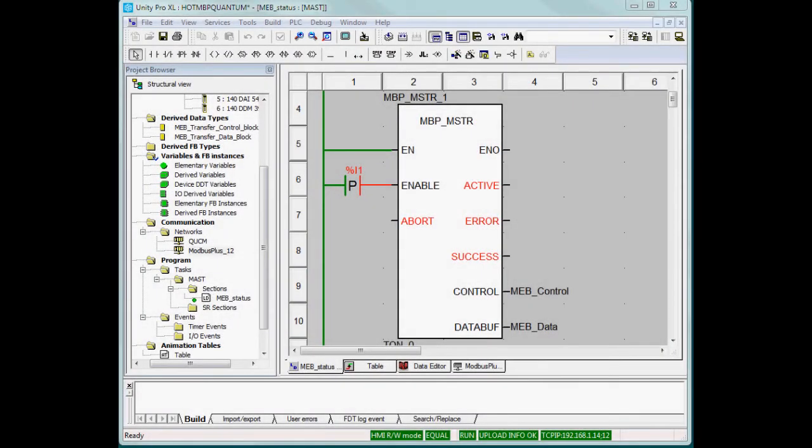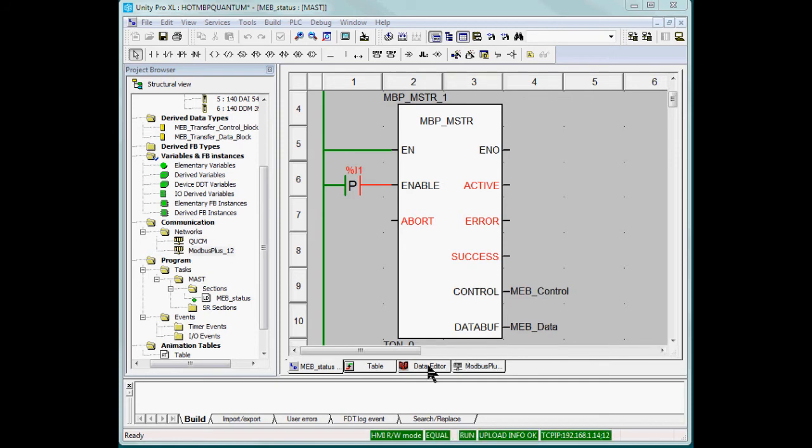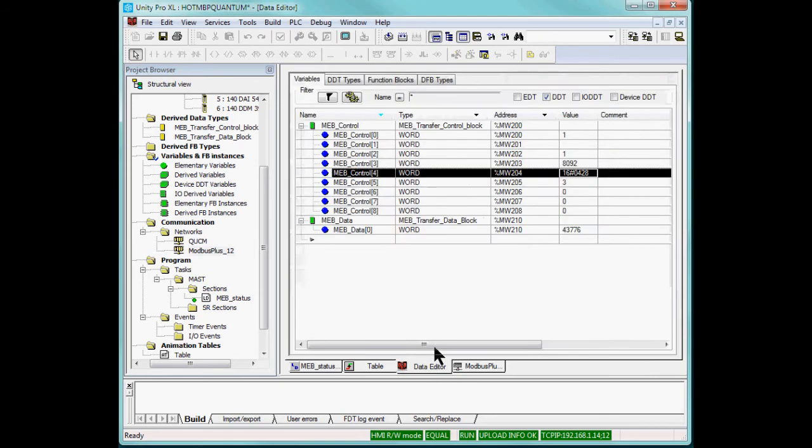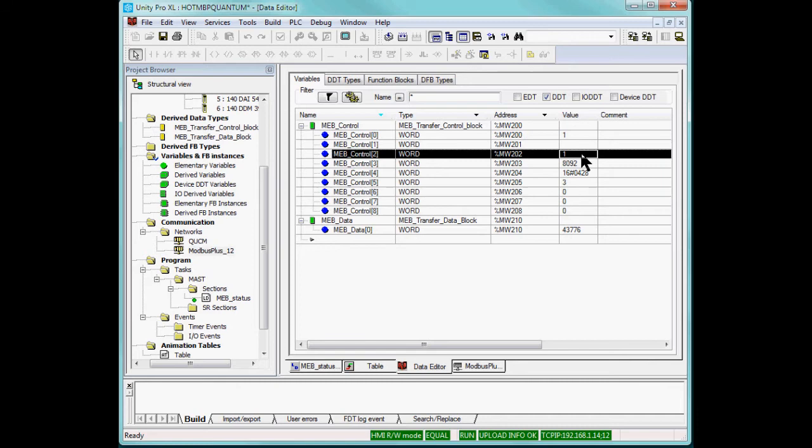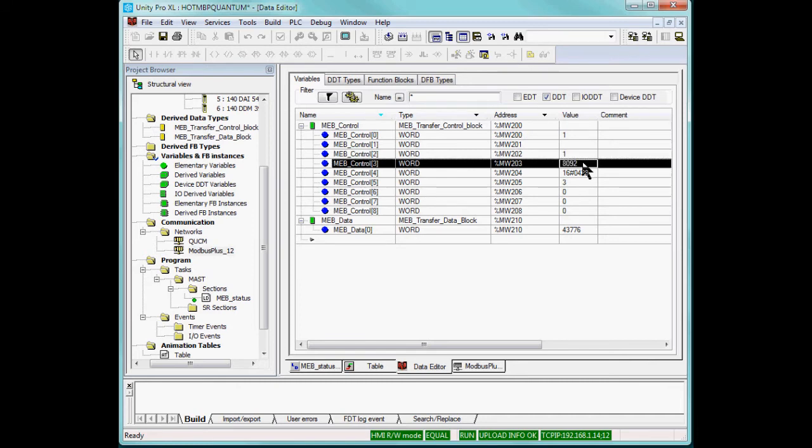It may be useful to have the PLC periodically force a transfer. A simple Modbus Plus MSTR write can make this happen. Full details are included in the user manual. The force transfer will only happen if the primary is satisfied that the secondary is fully functional.